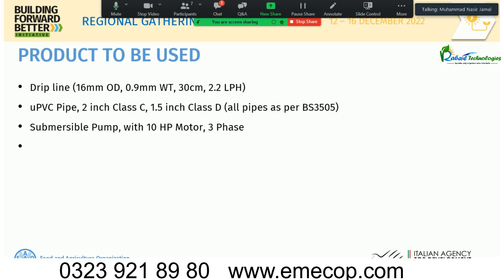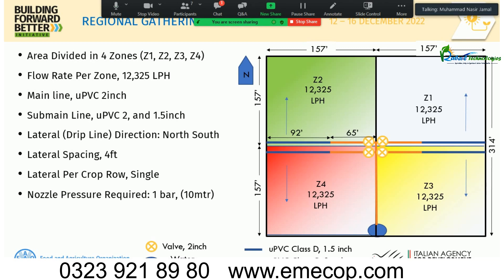The product used is imported Turkish drip line: 16 mm outer diameter, 0.9 mm wall thickness, with drippers every 30 cm (every 1 foot) discharging at 2.2 liters per hour. PVC pipe used is 2-inch Class C, telescoped with 1.5-inch Class D pipe. The submersible pump selected is 10 HP, three-phase.